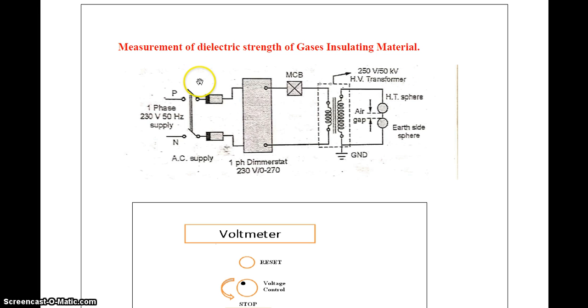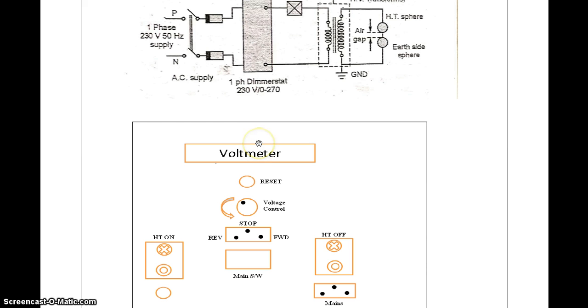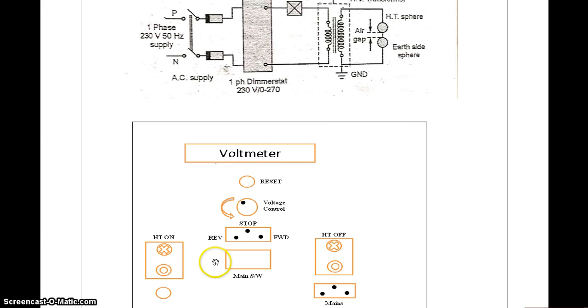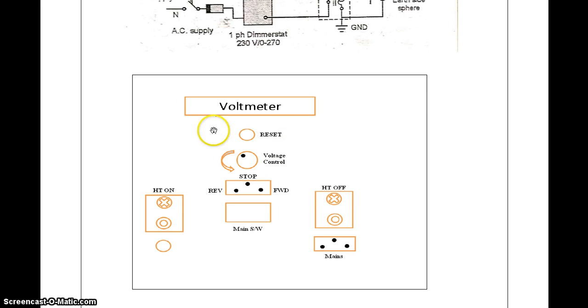Then the control panel used in measurement of dielectric strength of gaseous insulating material. First one is the voltmeter. The voltmeter indicates breakdown voltage. Then the reset button is used to restart the overall operation of the system. Then the voltage controller: in the reverse direction voltage decreases and in the forward direction voltage increases. Then the main switch. Then high tension on, high tension off. Then main switch and mains, that is the control panel of gaseous insulating material.